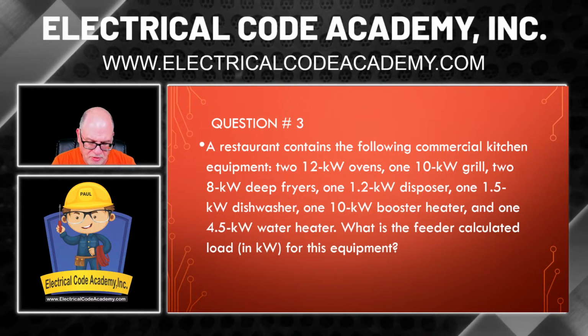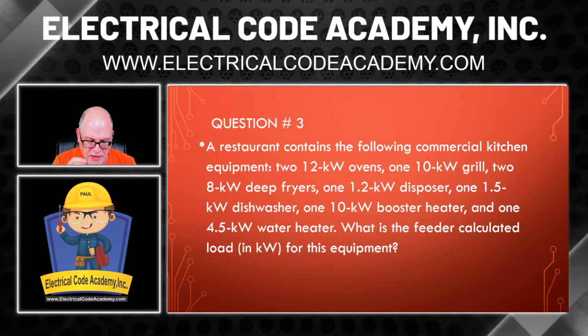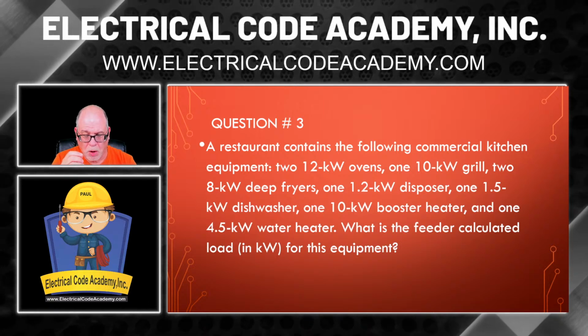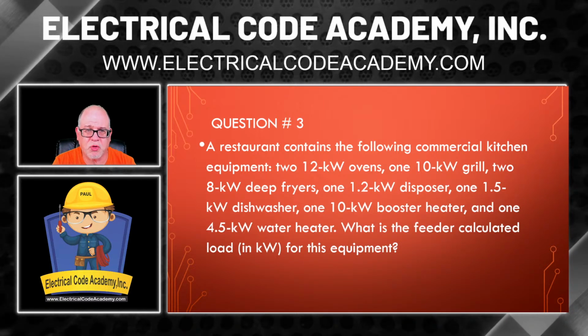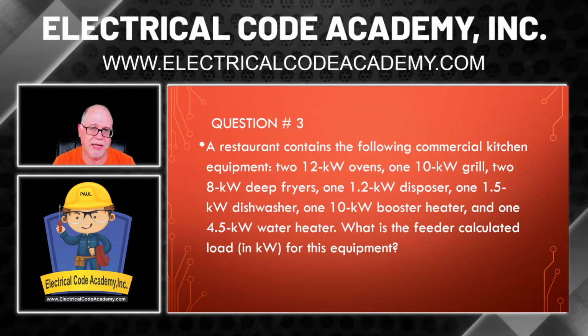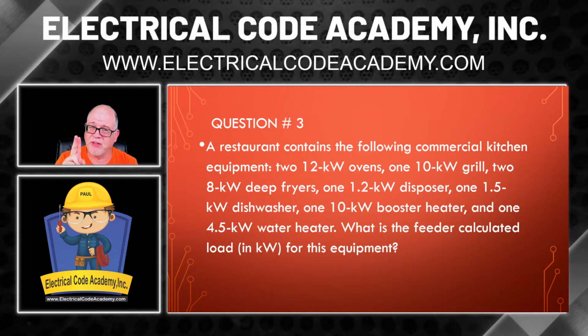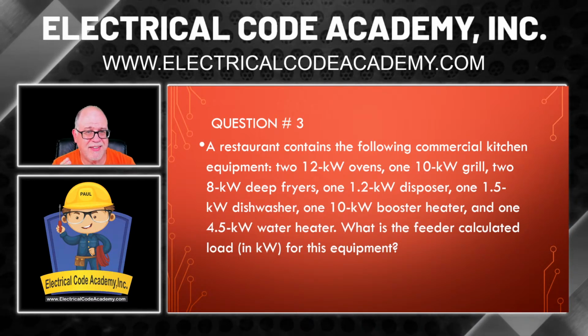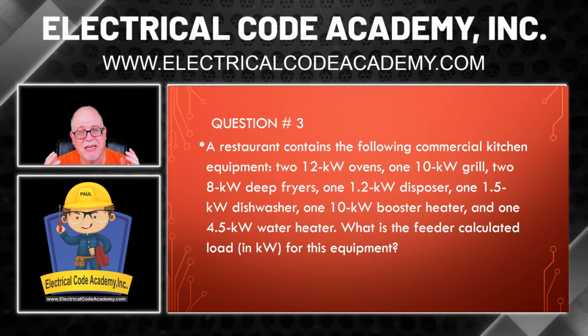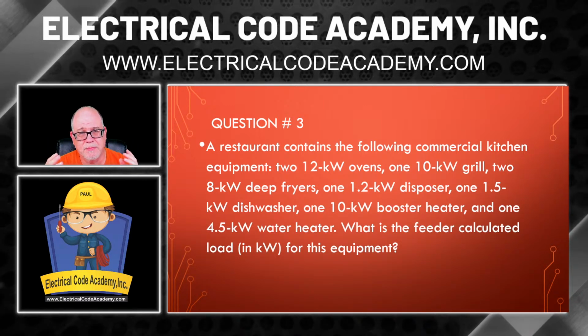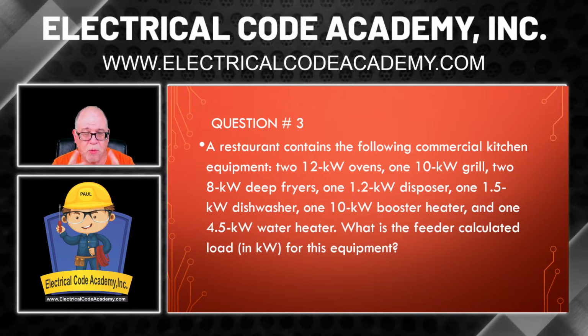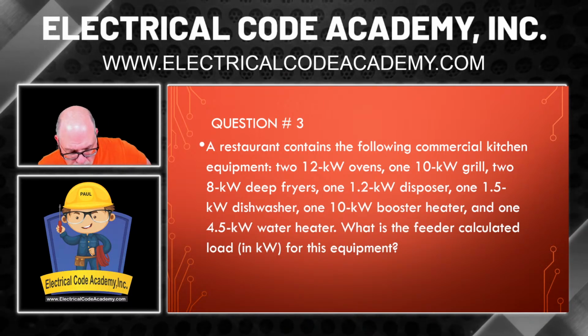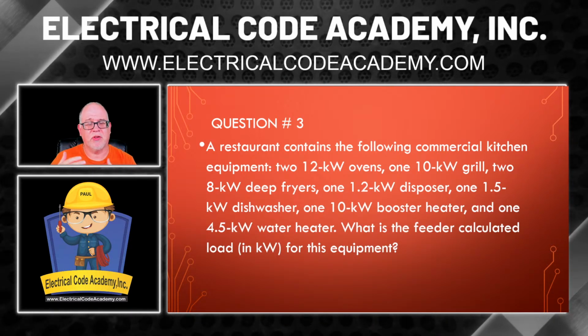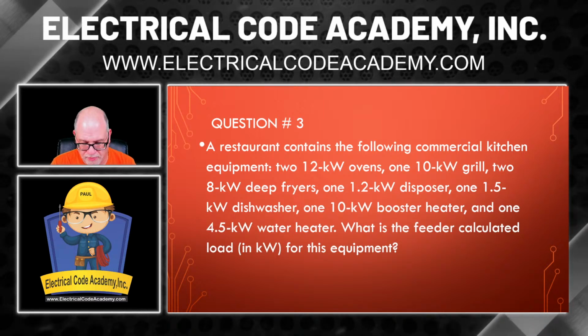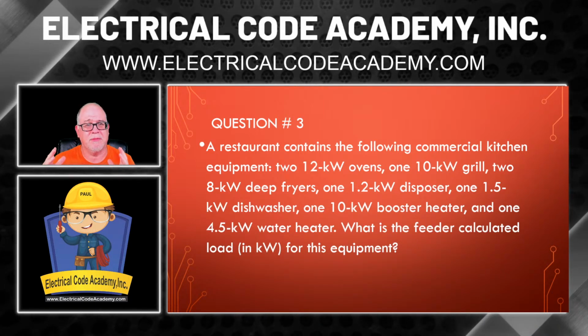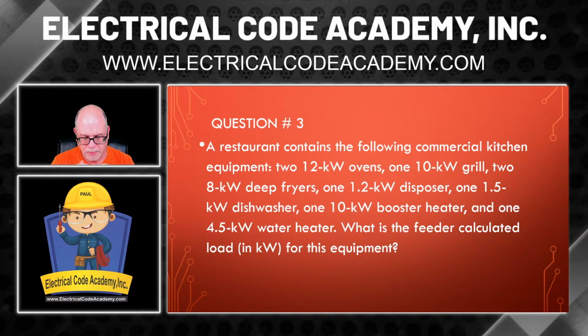So when we look at this, we're going to say, okay, well, we know that if there are any other multiple choice answers on there that are less than 24, we can throw those away. 24 is still on the table, but anything that's less than that, we throw away, because it can't be any less than the two largest pieces of equipment anyway, right? So we got that going for us there, okay? All right, and we're doing a feeder, so that makes sense what we're doing here. We're feeding a panel that's got just these loads in it, maybe, and that's what we're sizing this feeder for.